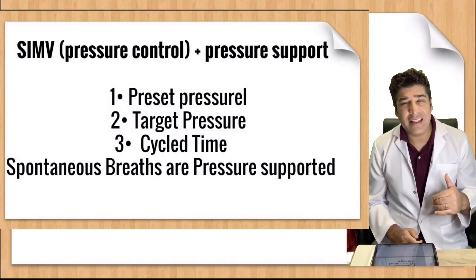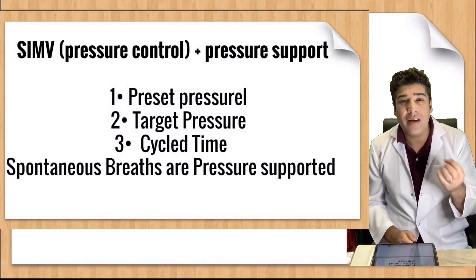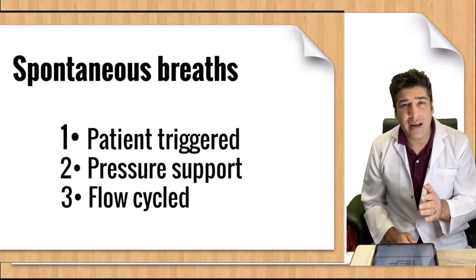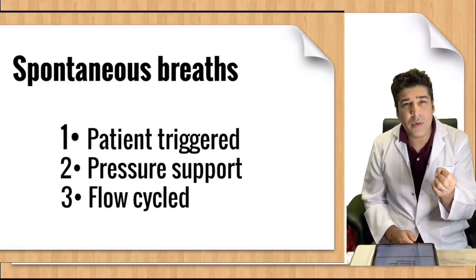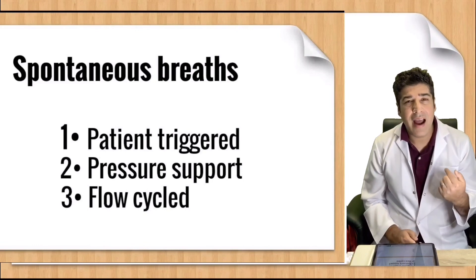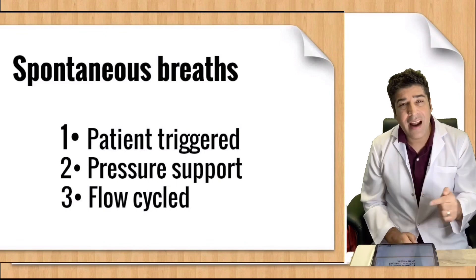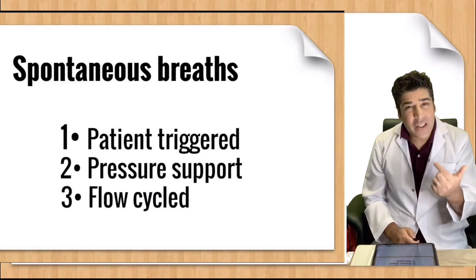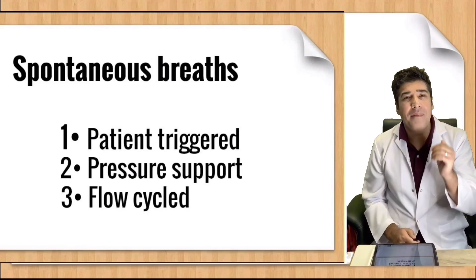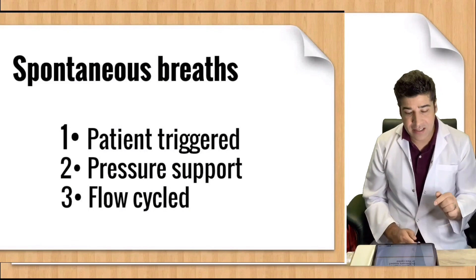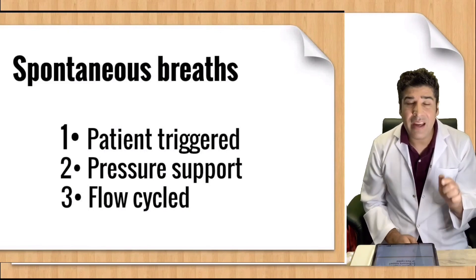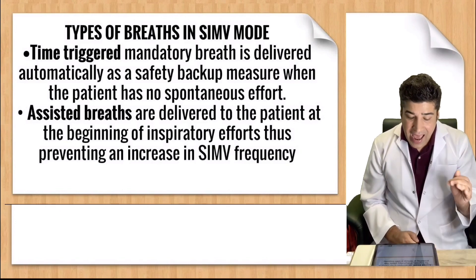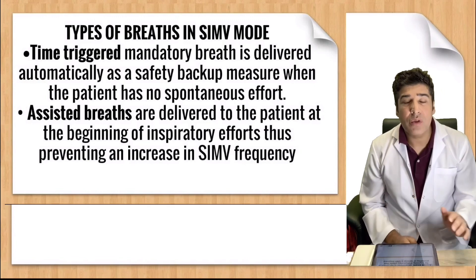What are the characteristics of spontaneous breaths when they are pressure supported? As discussed earlier regarding pressure support ventilation, it is patient triggered, flow cycled, and pressure targeted. These are the characteristics of spontaneous breaths on SIMV when they are pressure supported. Regarding types of breaths: time triggered mandatory breaths are delivered automatically as a safety backup when the patient has no spontaneous effort. Assist breaths are delivered to the patient at the beginning of inspiratory efforts, thus preventing an increase in SIMV frequency.